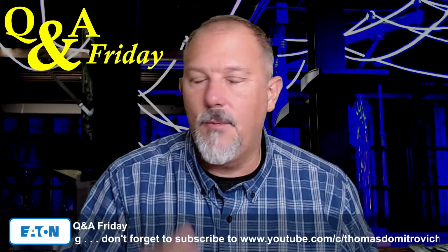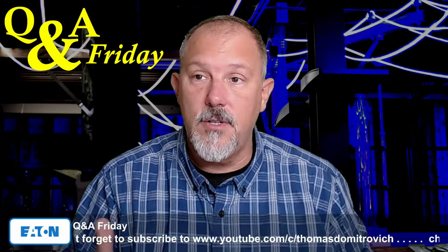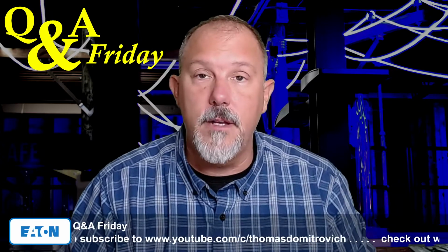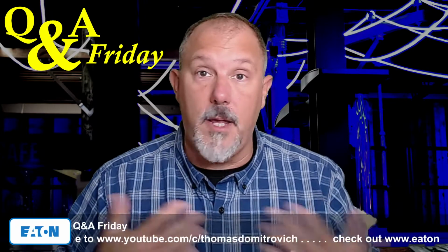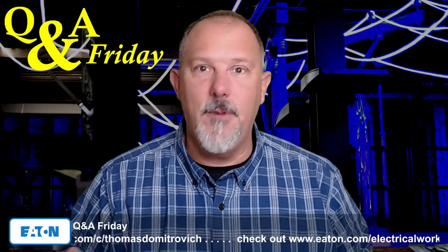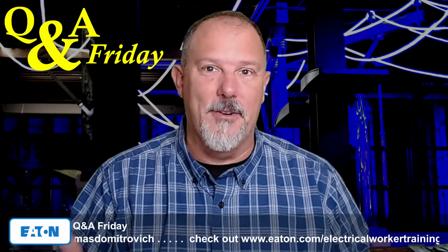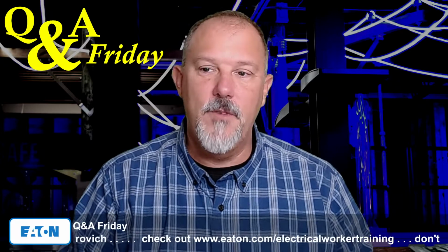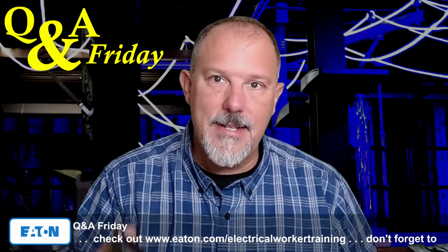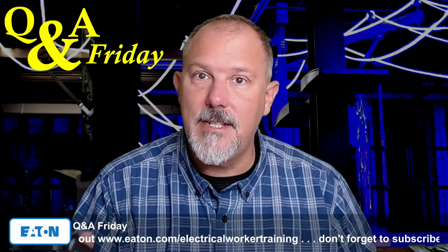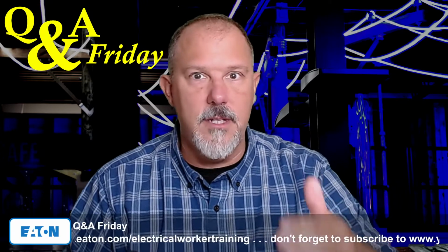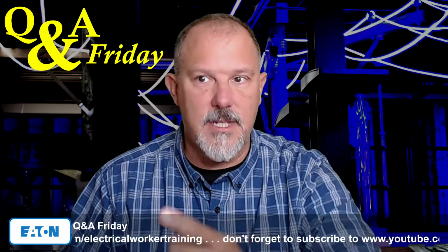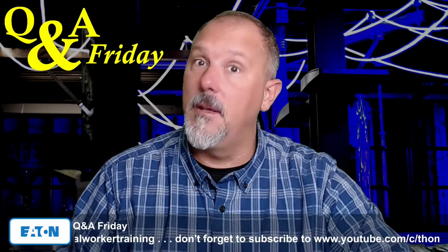And I say I want it to be approved. Now, an inspector could say, well, I'm going to approve it based on a conversation with me. Or the inspector could say, look, I'm going to accept some liability here, possibly if I approve it. So they'll want to know, is it listed? And if it's listed, then they'll look at the listing and make sure that the listing says it's going to do what this guy says it's going to do. Then that gives them the ability to approve it.